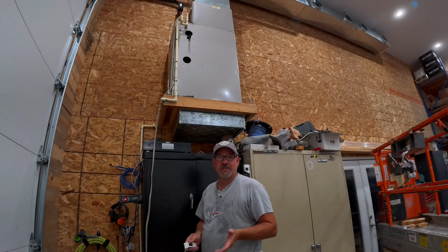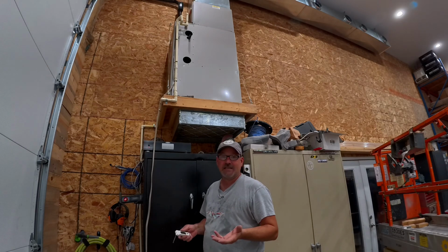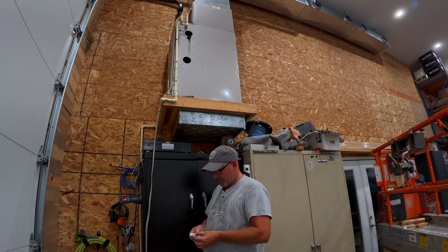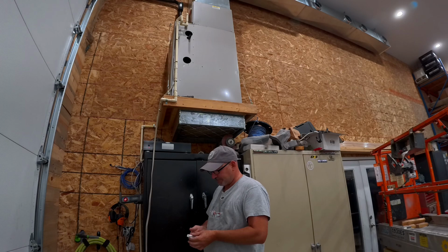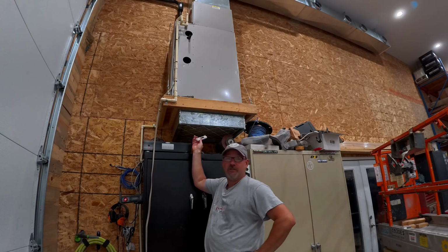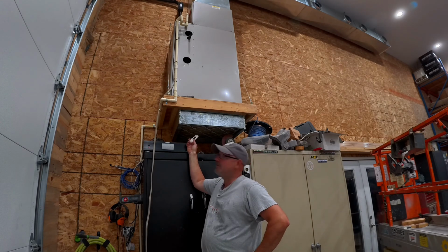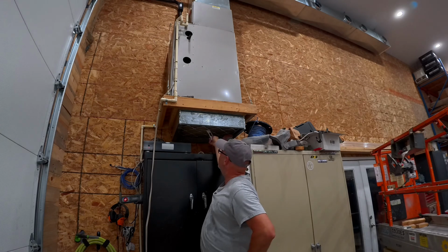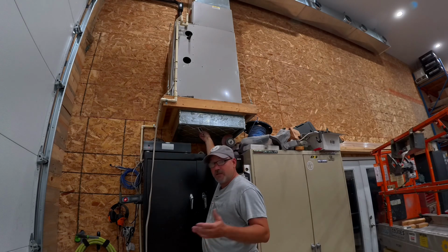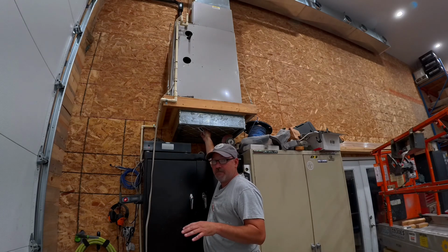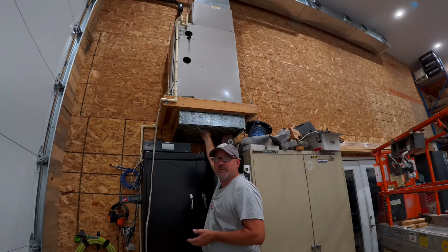Here's what we do. So I realize that every system's different, but they all have a basic design. We're out here in my shop today, obviously. And we're going to go to my filter on my furnace. And we're simply going to take our thermometer, we're going to slide up into the filter area. Anywhere around your filter is fine. And we're just going to check that temperature. And then we're going to record it.